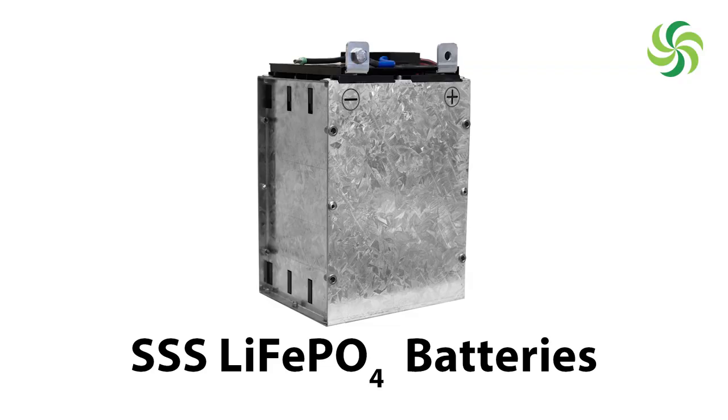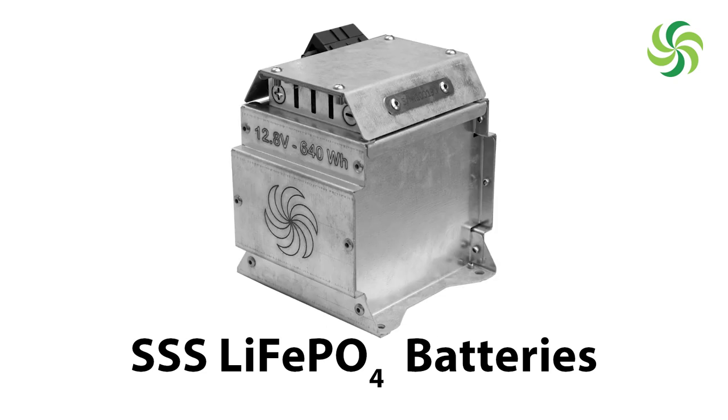In the distribution boxes, we would have loved to go entirely to lithium — we believe that's the way of the future, with the cycle ratio, time duration, and energy efficiency of a lithium battery offering a sustainable, long-term method of energy supply. However, currently, because certain DC systems are smaller, the lithium battery cost is too high to apply to both systems. So we've divided the two systems: both boxes look exactly the same, but we use a lead-acid battery in one to save costs for the client, and a lithium battery in the other, which delivers the right amount of energy at the right price.